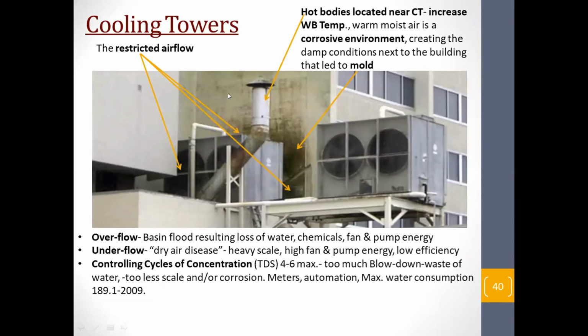The suction and discharge are both blocked, so this particular cooling tower may not work properly. In addition, there's a funnel going up. So the air here may be a bit hot, so that your wet bulb temperature may be at a higher value, and you will not be able to cool down condenser water as you wish. And I think you are already aware that we need to maintain the concentration or TDS with the number of cycles, avoid overflow, and avoid Legionnaires' disease by reducing the volume of water.